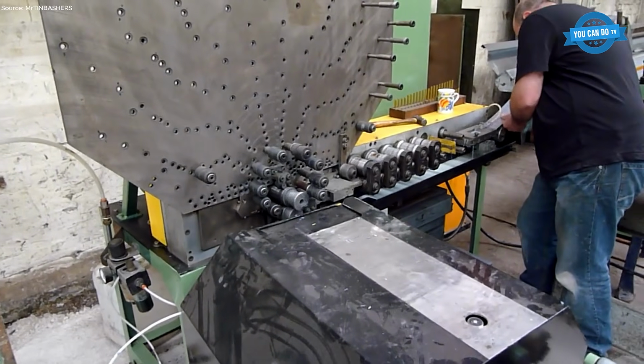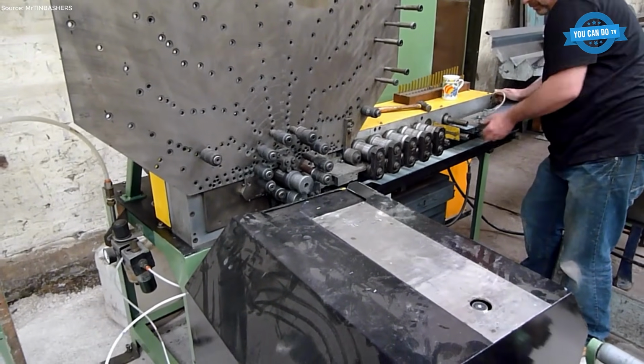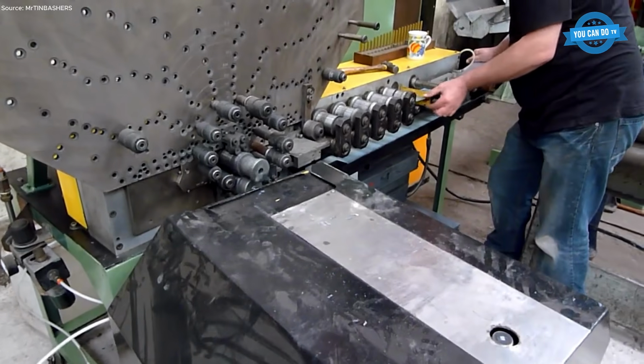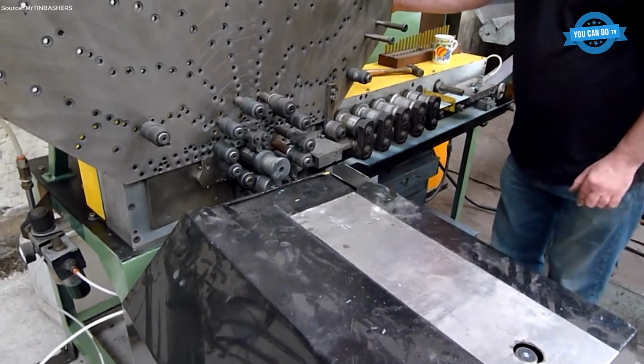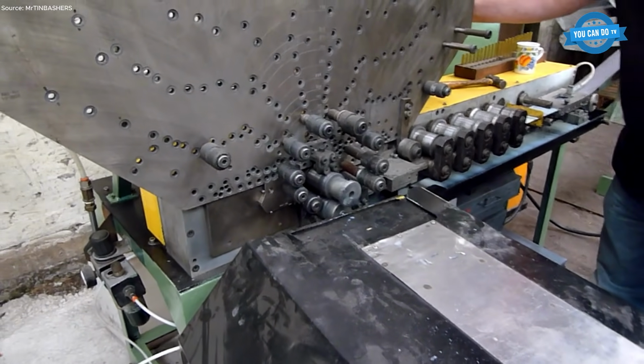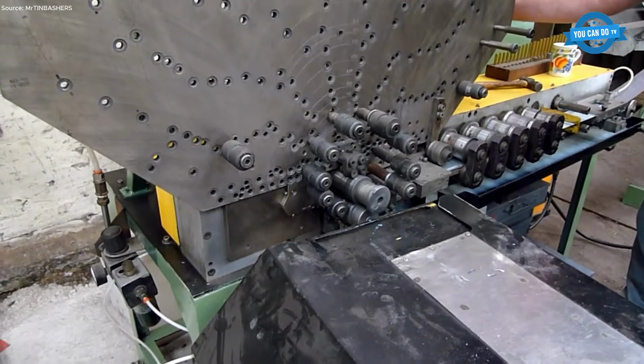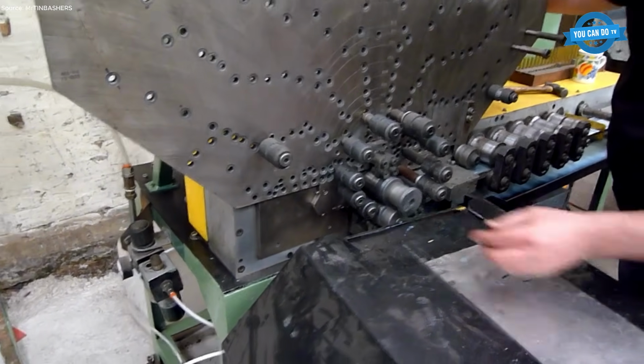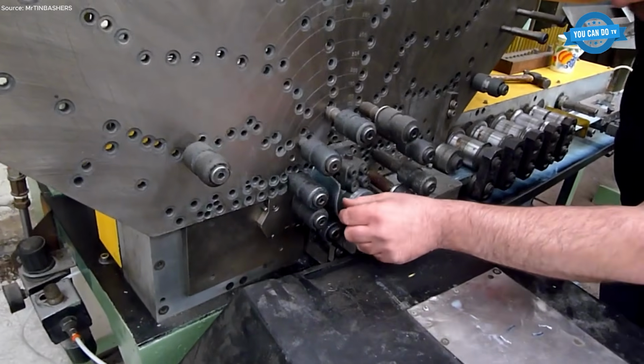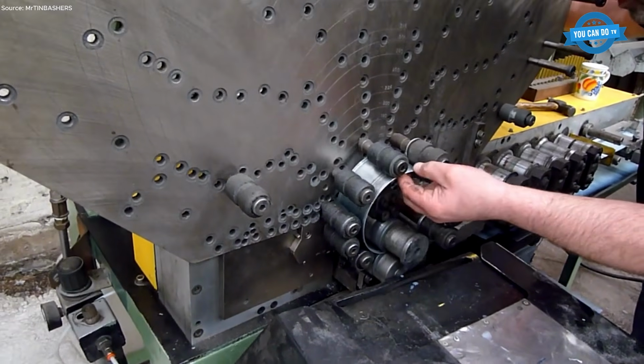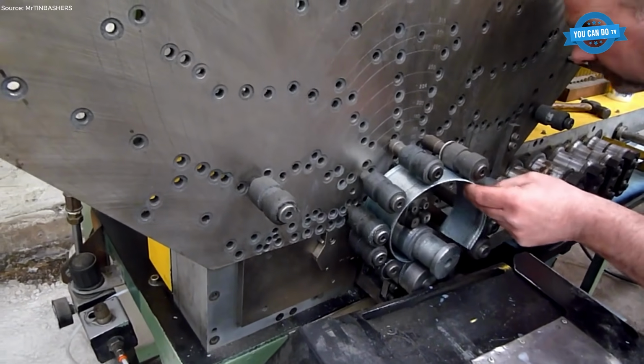A spiral duct line transforms flat steel coils into rigid, aerodynamically efficient spiral ducts through a continuous, highly controlled forming process. The operation begins with feeding a metal coil, typically galvanized steel or stainless steel, into the decoiler, where it is straightened and guided into the forming section.